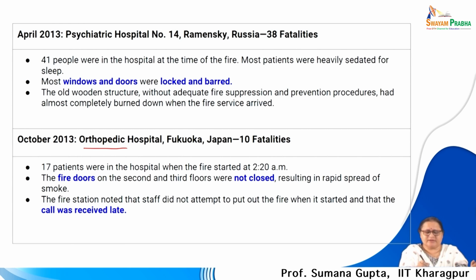17 patients were in the hospital when the fire started at 2:20 am, in the middle of the night, and the fire doors of the second and third floors were not closed, which led to smoke spreading rapidly, causing smoke choking and 10 fatalities. The fire station obviously responded, but since it was the middle of the night and there was no barrier between the two floors - that is, compartmentation was not formed - the fire and smoke engulfed 10 people.